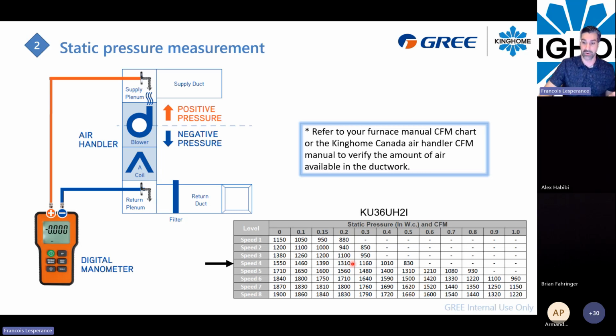So what I will do is change my speed to speed 3 and measure again, and if I get the same static pressure, I will reduce my CFM. And also I will be sure of what I am doing. It's not just trial and guess. You will be able to measure it and make sure you have the right amount of CFM passing through that coil.